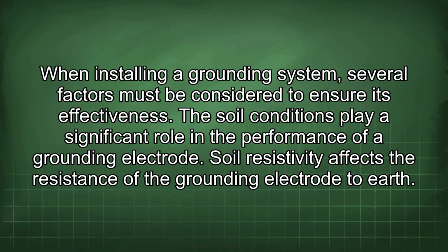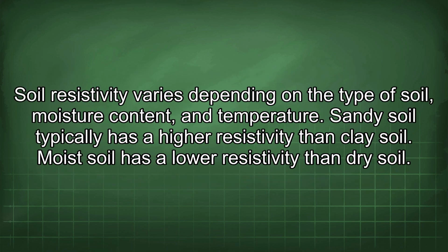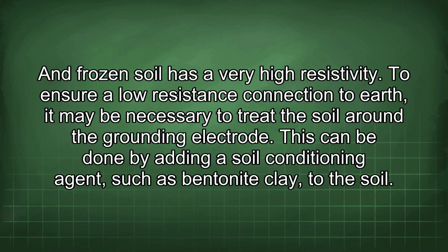When installing a grounding system, several factors must be considered to ensure its effectiveness. The soil conditions play a significant role in the performance of a grounding electrode. Soil resistivity affects the resistance of the grounding electrode to earth. Soil resistivity varies depending on the type of soil, moisture content, and temperature. Sandy soil typically has a higher resistivity than clay soil. Moist soil has a lower resistivity than dry soil, and frozen soil has very high resistivity.